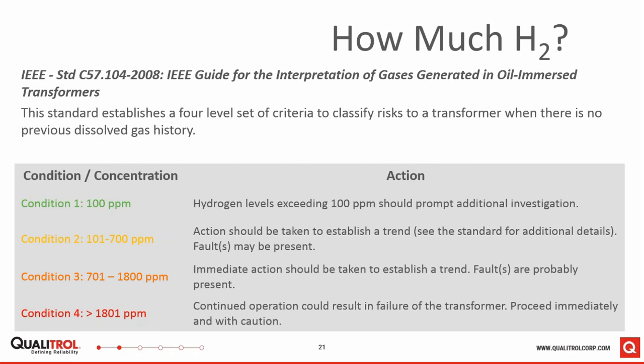But due to the smaller volume of oil, smaller transformers can have significantly faster rates of change of hydrogen, just due to the smaller volume of oil that the hydrogen's dissolved in. And so most of the time you never like to see hydrogen in your transformer, but I have found through experience that smaller transformers can have significantly larger amounts of hydrogen than what you typically find in large power transformers. But according to Dr. Duval, overall, there's not a significant difference. If you have high levels of hydrogen in a small transformer, it is something that you definitely want to be concerned about, just like you would be if you had high levels in a larger transformer.